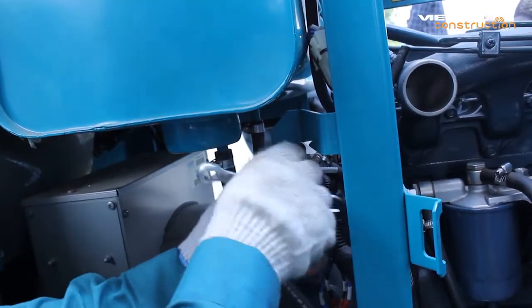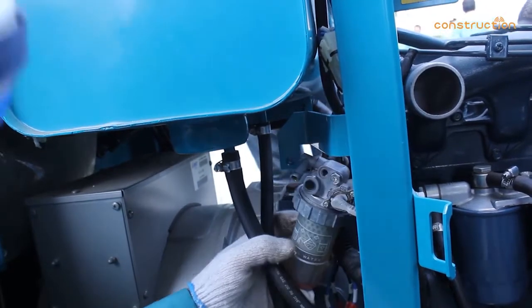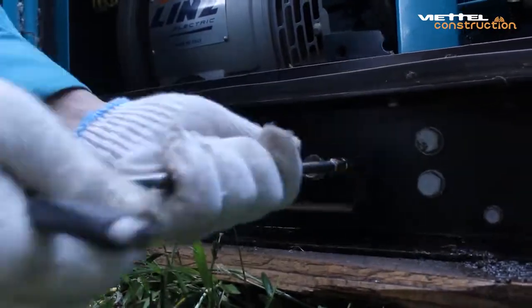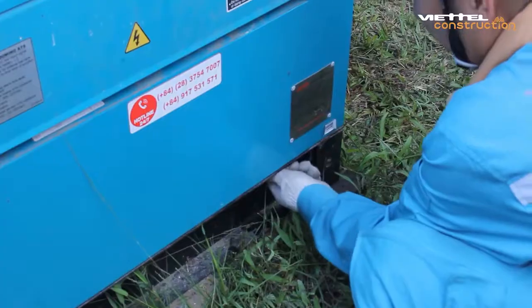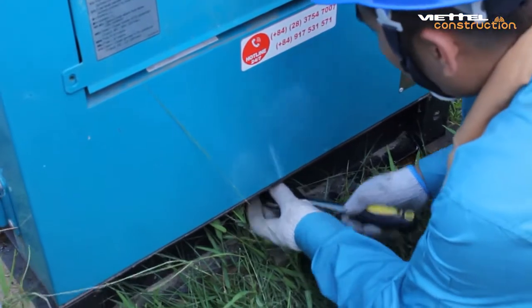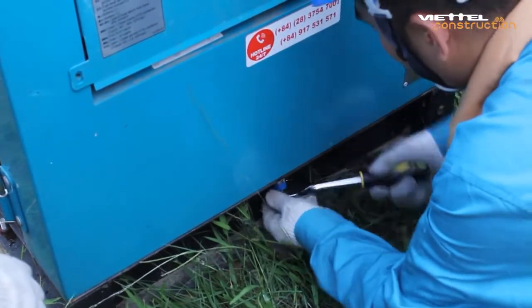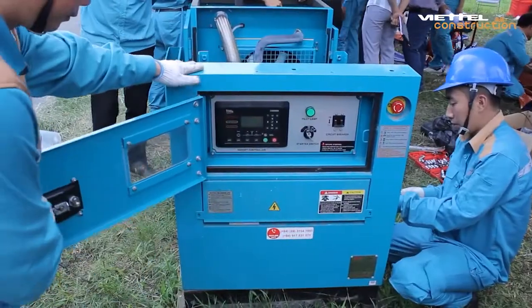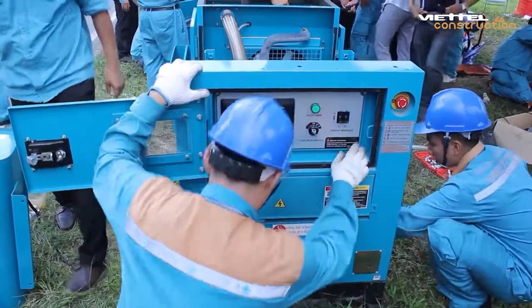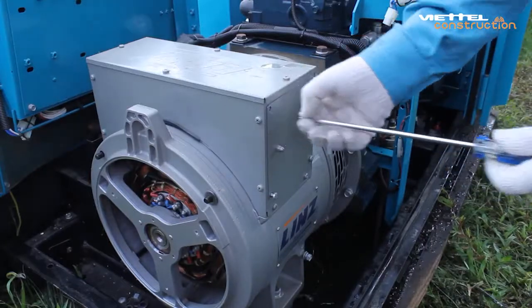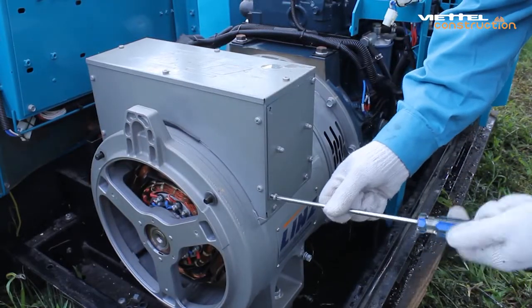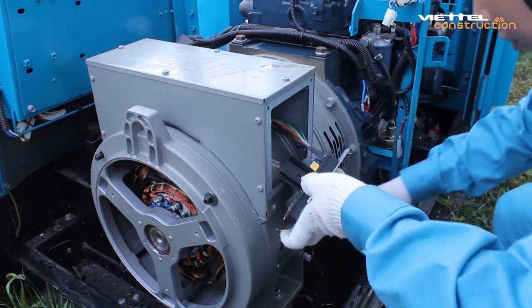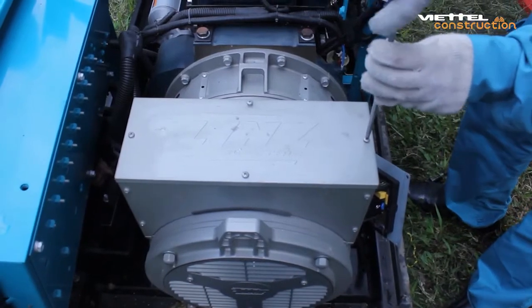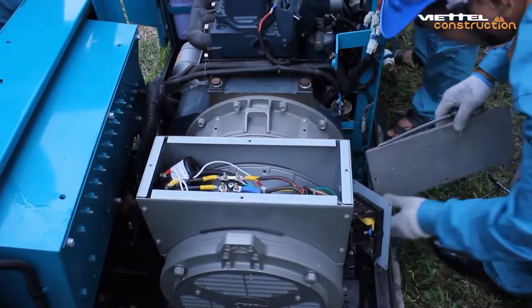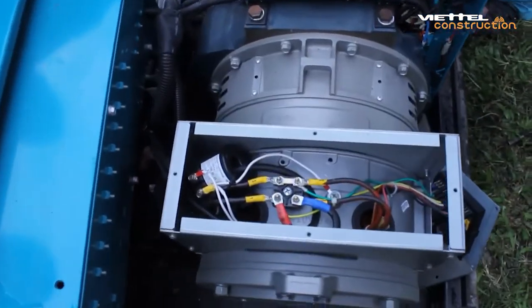Remove the water filter. Remove the oil drain pipe. Remove the control box. Remove the cover of the AVR board. Remove the top cover of the stator windings. Tighten all the connection point. Check the contacts of the electrical system, the AVR board.